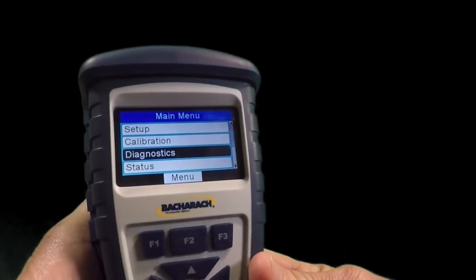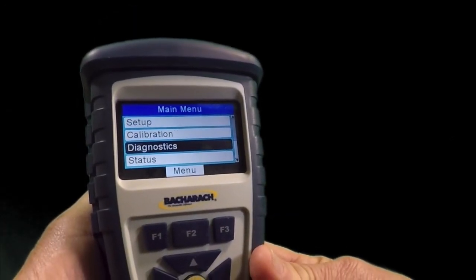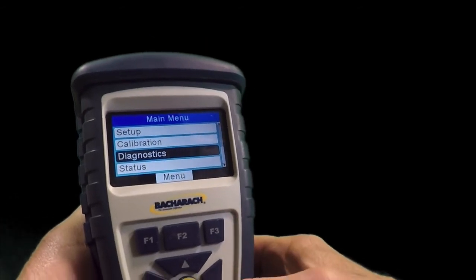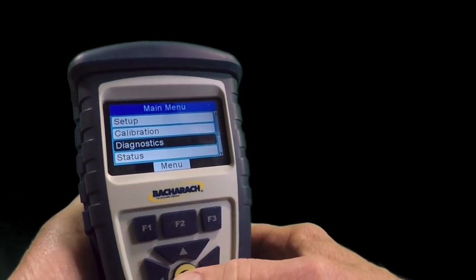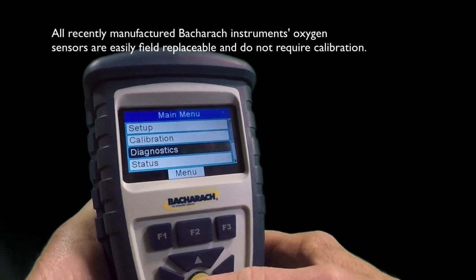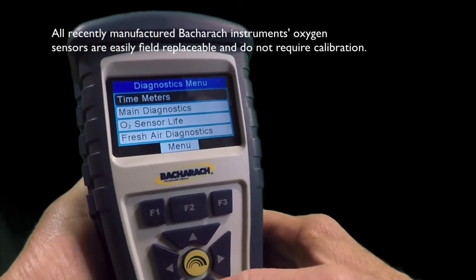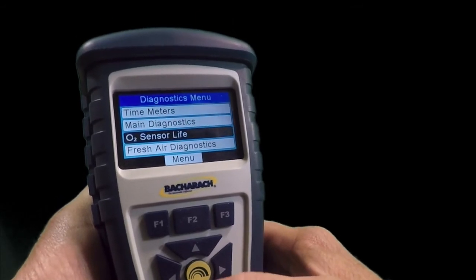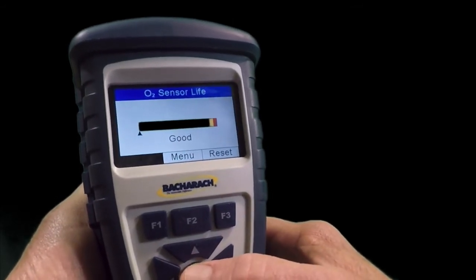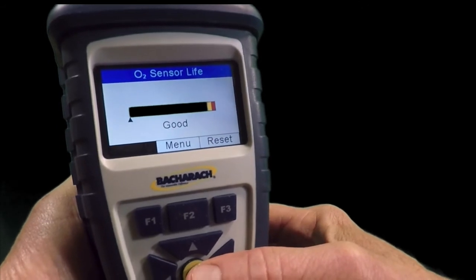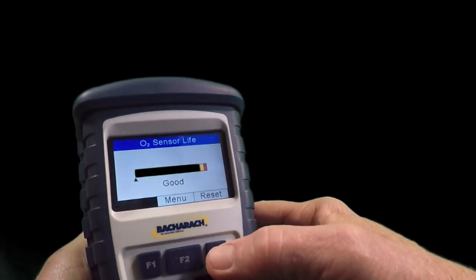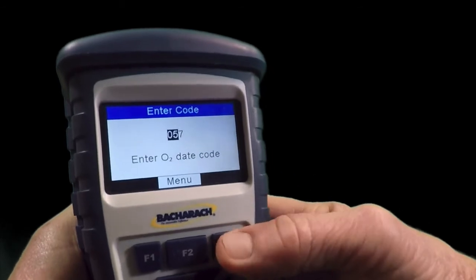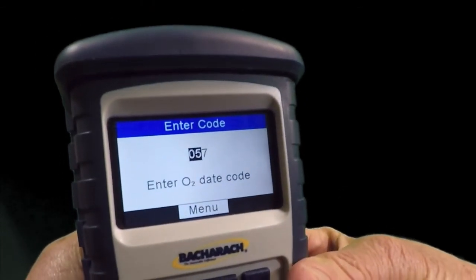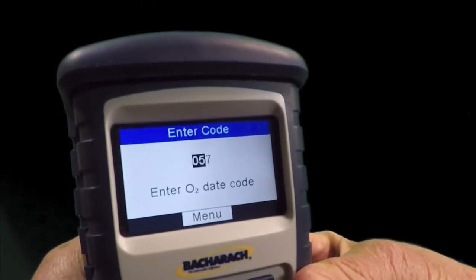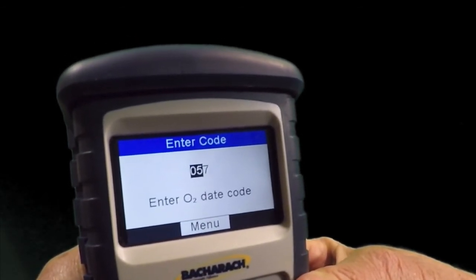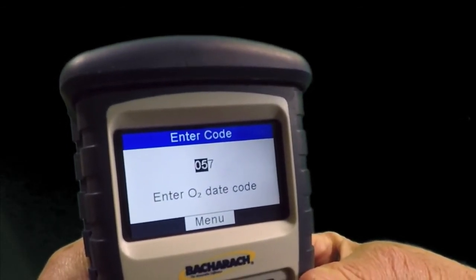The last area I want to point out is one common mistake I see being made. Go to the diagnostics section, and this is particularly when you replace an oxygen sensor. Scroll down to O2 sensor life, hit enter. You'll notice this sensor is good. If you hit the F3 button or reset, you'll see that the date code on the sensor that's in this instrument is 057. That means that it was manufactured in May of 2017.